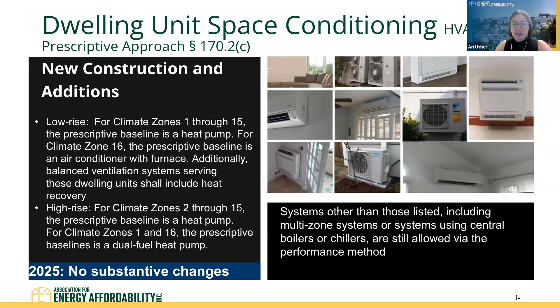Let's go on to alterations. Next slide, please. The most common that you'll see will be a complete change out of your space conditioning. And for alterations, the baseline is your heat pump again for climate zones other than 1 and 16. And just a note here that a supplemental heating unit may be installed, provided that the unit thermal capacity does not exceed 2 kilowatts or 7,000 BTU per hour and does need to be on a 30-minute timer. And another note, air sealing requirements do apply for existing or new ductwork in your alteration projects. So if you're working with ducted systems, you will need to be complying with duct sealing and leakage testing. You'll have those requirements and testing requirements as well.